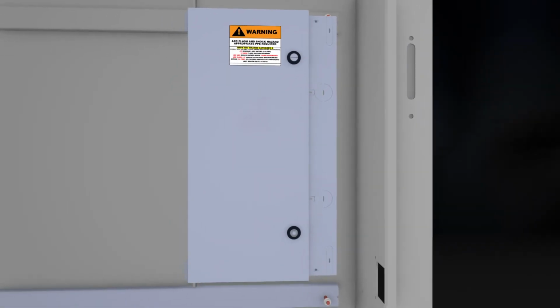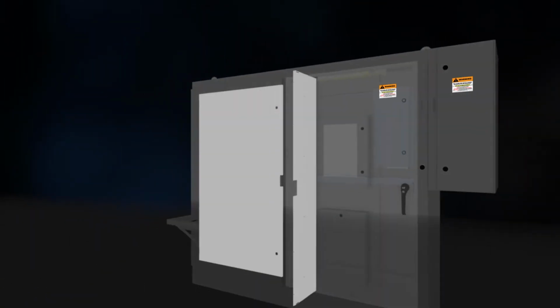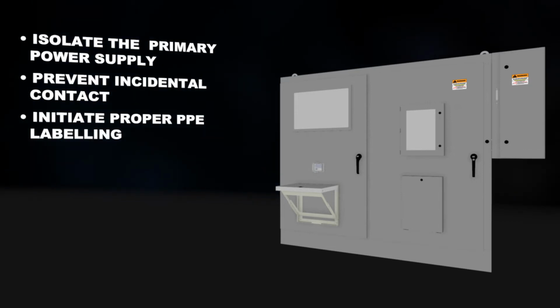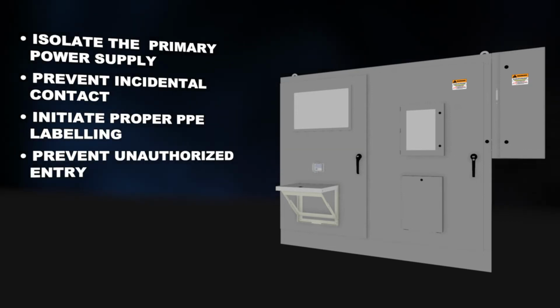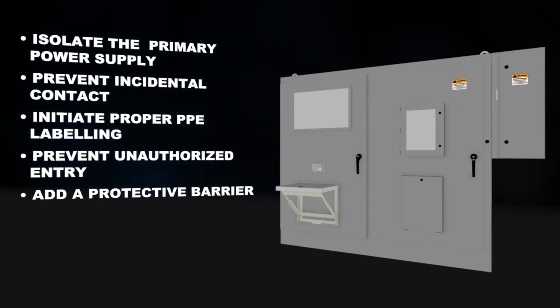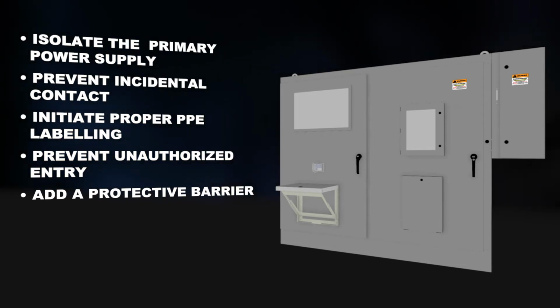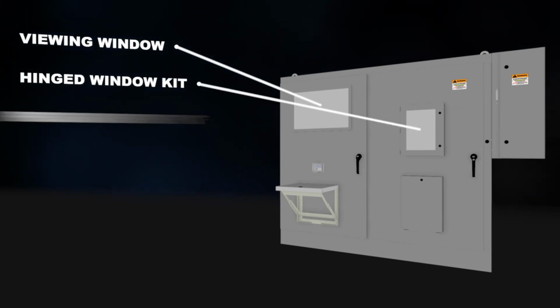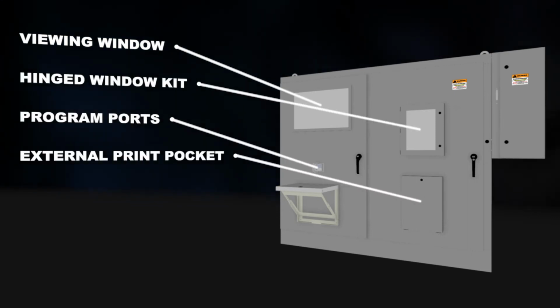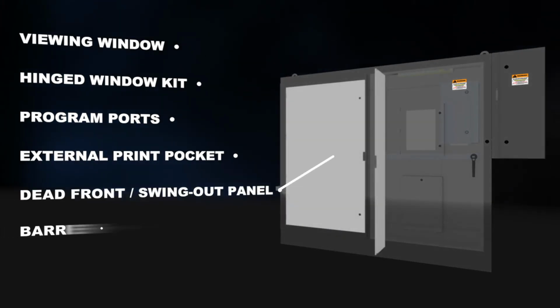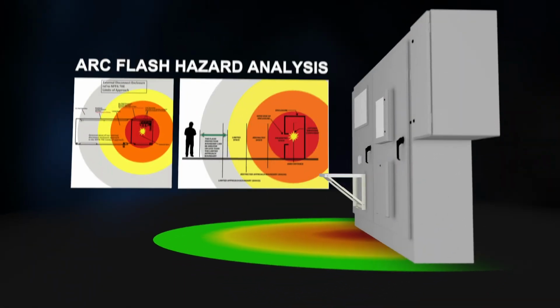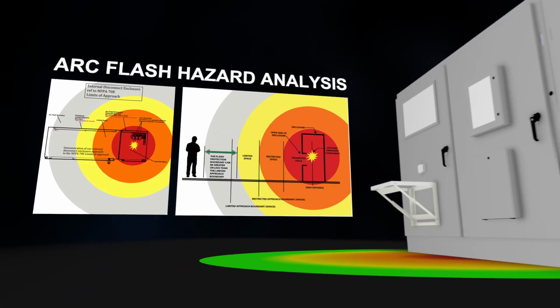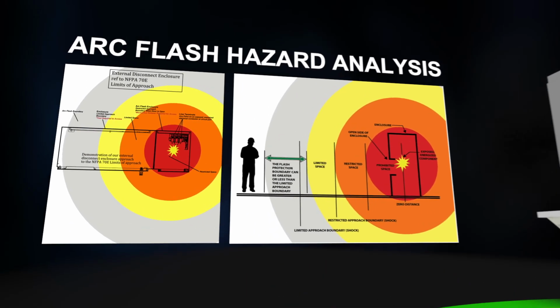The intent and purpose of the internal disconnect enclosure, external disconnect enclosure, or barriers are to isolate the primary power supply and prevent incidental contact with live feed, to initiate appropriate PPE labeling for entry, to help prevent unauthorized entry, and to add a protective barrier between the worker and the arc flash hazard. Other accessories that are offered can simply help prevent the need to access the enclosure in order to evaluate, troubleshoot, or service some equipment.